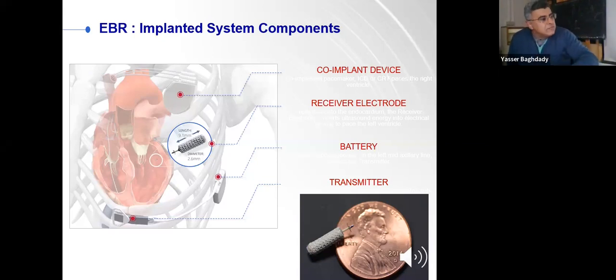So this is true left ventricular endocardial pacing via a very, very small electrode that's about 9mm in length that we insert through the sheath, as I'll show you. How does this work? It's almost like a subcutaneous ICD type of battery. This is the battery that gets inserted in the axillary area. It has a cable that connects to a transmitter, and the transmitter basically uses sound. So this is ultrasound that will activate this endocardial LV electrode.